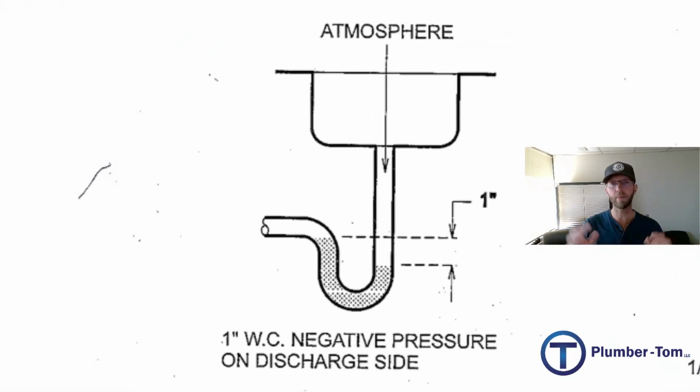That means we're going to hook up pipes to provide airflow. That means air can come in when it's needed if there's a negative pressure. It can push out if there's a positive pressure. And by doing so, we maintain the trap seal of the fixtures within 1 inch. Now this is a fluid. The fluids can move with pressures. Try this experiment sometime. Next time there's a big windstorm in your area, just go have a look at your toilet bowl. Open the lid, look at the water. If there's enough air pressure pounding on the pipes, the vents, out the roof, you'll actually see a fluctuation in the water level. It's kind of fun to watch.